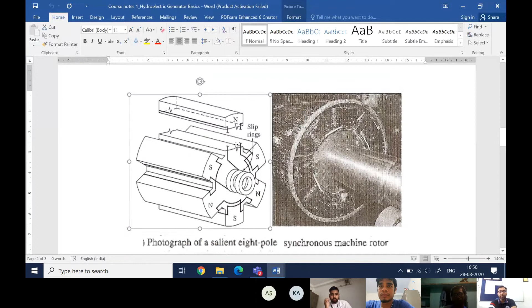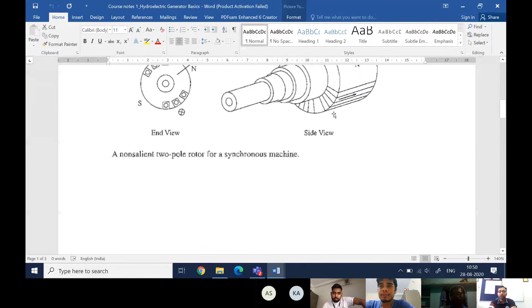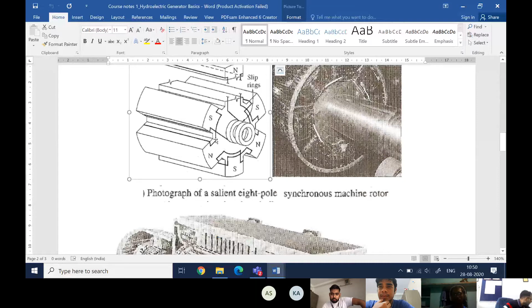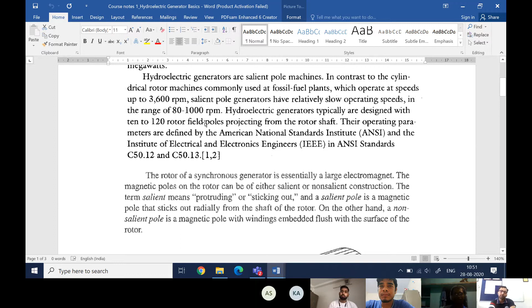Those high torques can be sustained by the cylindrical type, and that's why for higher RPMs, 3000 or 3600 RPM up to that range, you can use a cylindrical rotor. And a salient pole rotor will always have a limit. It can't be used above 1000 RPM. So a salient pole rotor is good in the range from as low as 80 RPM up to 1000 RPM, and for higher RPMs, above 1000 RPM, 1500, 1800, in that order, 3000, 3600, you can have a cylindrical rotor. So it has to do with the structural stability. Nothing electrical here, just structural stability.